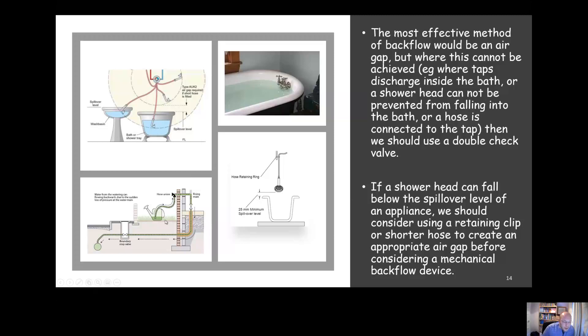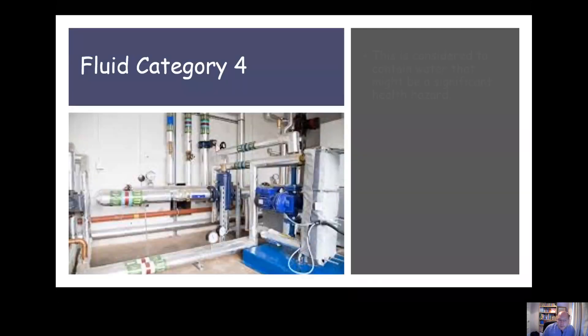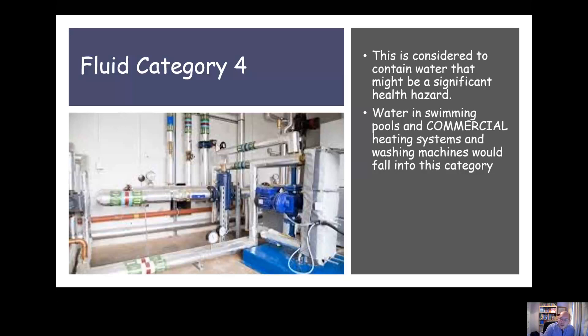Another place where we must always use a double check valve is at an outside tap — a hose union bib tap. The Guild loves to ask about this, so it's worth noting. You can see the reason in the picture: on a hose union tap we're going to connect hoses, and that hose could be draping in a puddle, eliminating any air gap. So whenever we fit a hose union tap, we must fit a double check valve alongside it.